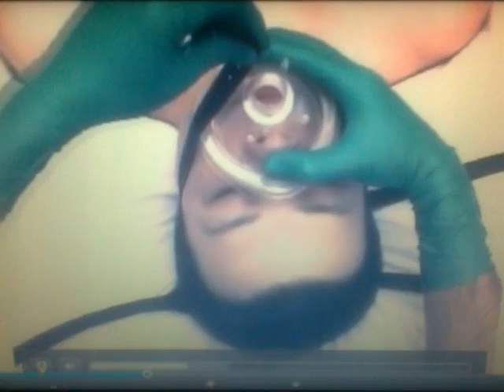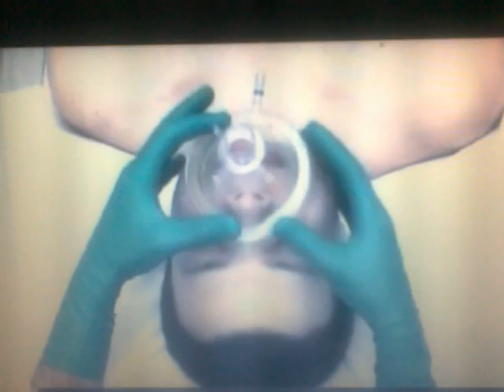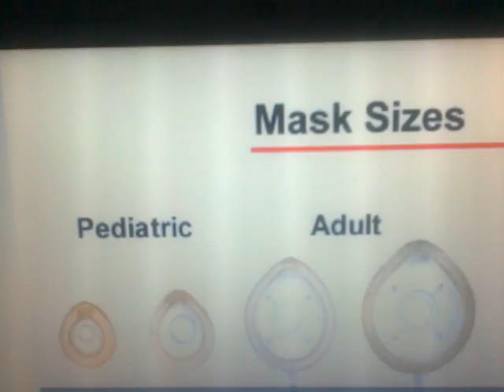The rim of the mask provides the seal with the face. Many masks have an inflatable cushioned rim, which creates a better seal with facial contours. Some masks have a malleable body, which can be molded to the face, thus reducing dead space. Masks equipped with a ring with hooks can be used with a mask strap to better hold the mask on the face, but may prevent rapid removal of the mask, for example, when suctioning the oral cavity is necessary. The connector of the mask is a standardized 22 mm diameter orifice and connects the mask to a bag valve device. To maintain a good seal, it is imperative for the mask size and shape to conform to the facial anatomy. This is particularly important in the pediatric population. Thus, several mask shapes and sizes should be readily available.